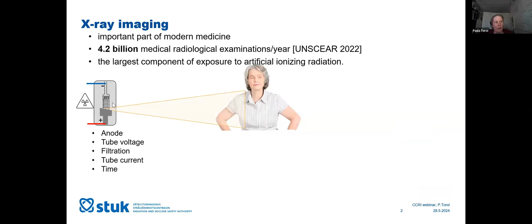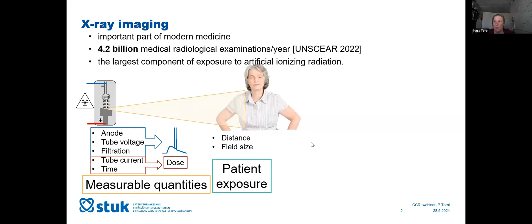When we talk about an X-ray system, we have the X-ray tube, the anode, and the tube voltage, which can be changed. We can change the filtration. This defines the spectra. Then we can adjust the tube current and exposure time, and with this adjustment, we can impact the dose. So the dose at this level is the measurable quantity. When we add the distance and the field size, we can also talk about the patient exposure. And when we take into account the patient properties, we can estimate the patient dose, which is different from the measurable quantities we talk about when we talk about dosimetry and dosimetry measurements.